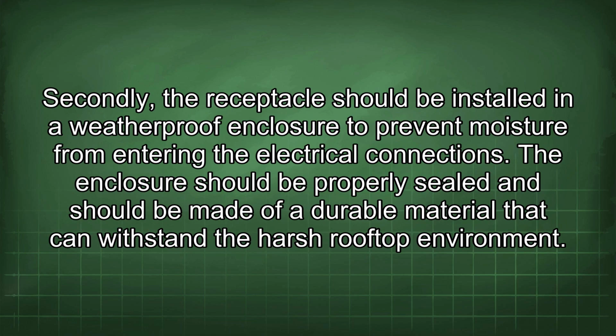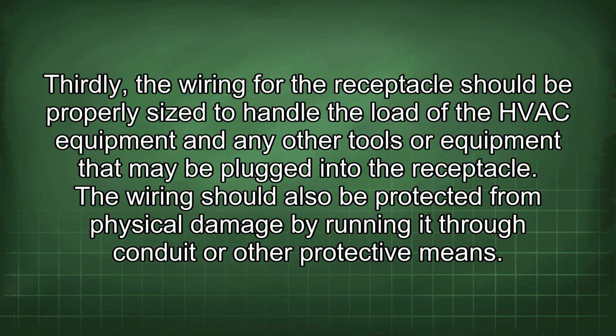Secondly, the receptacle should be installed in a weatherproof enclosure to prevent moisture from entering the electrical connections. The enclosure should be properly sealed and should be made of a durable material that can withstand the harsh rooftop environment. Thirdly, the wiring for the receptacle should be properly sized to handle the load of the HVAC equipment and any other tools or equipment that may be plugged into the receptacle. The wiring should also be protected from physical damage by running it through conduit or other protective means.